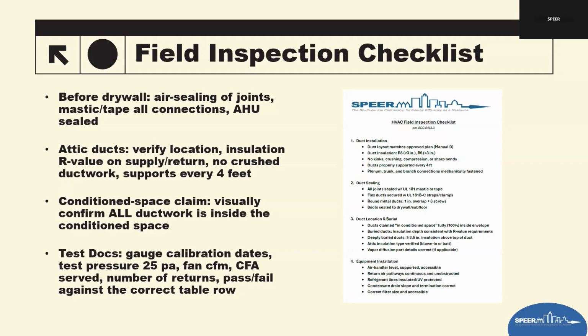I walked a house over the weekend that looked pretty much finished for the duct system. It was a trunk and branch, and if the duct system was tested, it probably would have passed. However, one of them wasn't even connected to the trunk. So eventually they'll have to cut sheetrock. We found it and told the builder he's going to get that fixed, but it was hiding in a valley of a floor truss system. You couldn't really see it unless you looked from a certain angle. So the duct was not connected, which means the leakage won't show on a duct test, but eventually someone will say there's no air coming out of this supply. The only way to fix that is to cut sheetrock, cut through the trunk, and add the duct. So verify all those things while walking an inspection in the field.